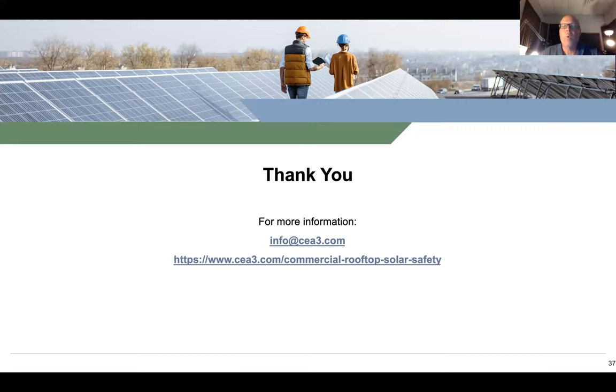Okay, another question here. I'm asking what your experiences are with root cause analysis for manufacturing defects, examples like rapid shutdown devices and such. We are performing root cause analysis on thermal events on inverters right now, rapid shutdown devices, racking systems. We have the capability, we have labs that can test components. Some of the components you saw there in our presentation, we do the investigation in the field, deliver it to the lab, and they do the destructive testing and the detailed root cause analysis in addition to what we found in the field. So we're doing quite a bit of those right now.